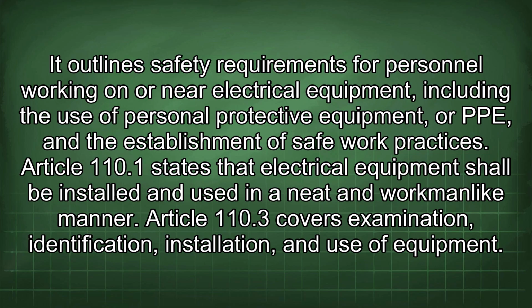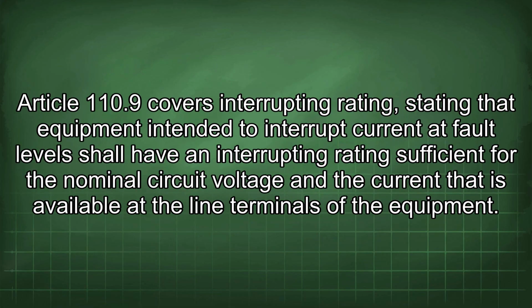It outlines safety requirements for personnel working on or near electrical equipment, including the use of personal protective equipment, or PPE, and the establishment of safe work practices. Article 110.1 states that electrical equipment shall be installed and used in a neat and workmanlike manner. Article 110.3 covers examination, identification, installation, and use of equipment. Article 110.9 covers interrupting rating, stating that equipment intended to interrupt current at fault level shall have an interrupting rating sufficient for the nominal circuit voltage and the current that is available at the line terminals of the equipment.